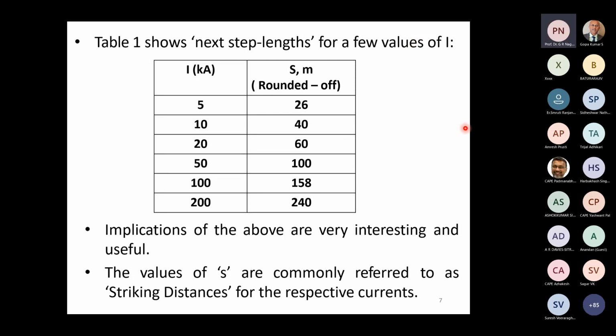This table 1 shows so-called next step lengths, values of S for a few values of I, typical ranges. Suppose you think of the lowest current: the 99% probability current is 5 kiloamperes. 2 kiloamperes has also been seen, 2 to 3 kiloamperes, but the probability is extremely small. So as a round figure, 5 kA has been considered here. Then 10, 20, 50, 100 and 200 kiloamperes have been considered. And from the equation S equal to 10 I to the power of 0.6, for 5 kA the rounded-off value of S is 26 meters.